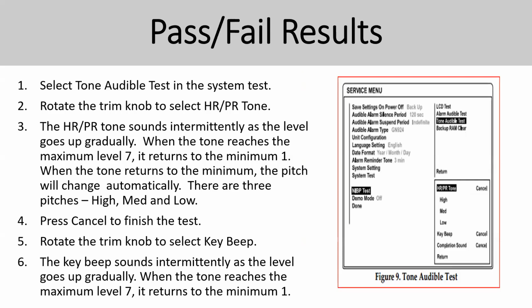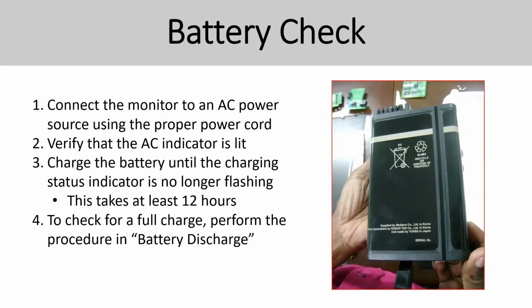So pass and fail results depend on your checklist. If your checklist reading is complete and everything is passed, you can put pass there. Battery check is basically checking the battery by removing the power cord, seeing whether the incoming power transfers to the DC mode, to the battery mode. If not working, please check the battery and try to charge overnight and check if it works.